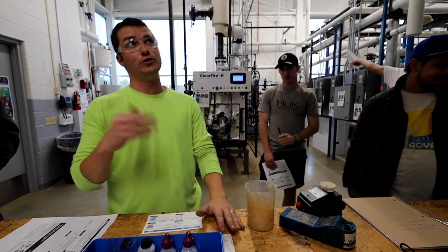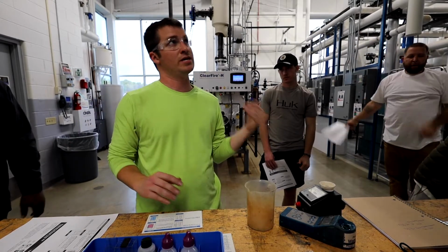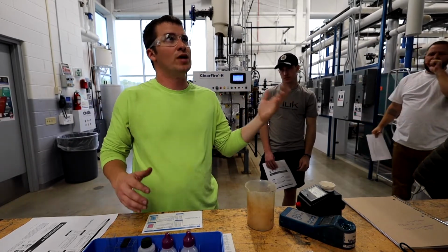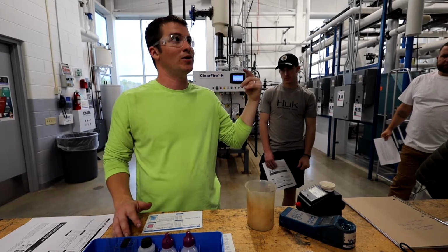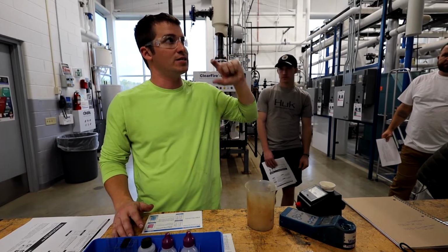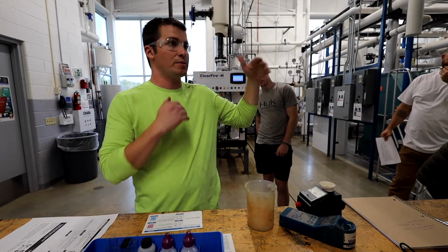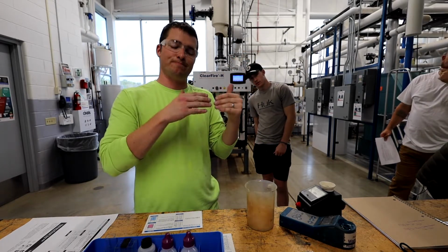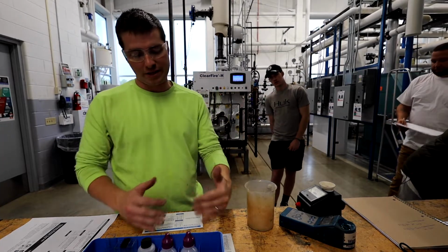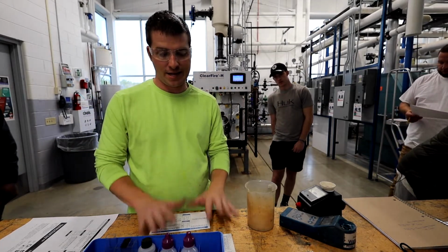You know, if you feed too much sulfite, you're going to lower your alkalinity. So what does that mean to you? That might not mean much, but to me, I can tell, okay, we added too much sulfite. I see that our O alkalinity is lower in our boiler overall. I know I need to reduce my sulfite because of its impact.